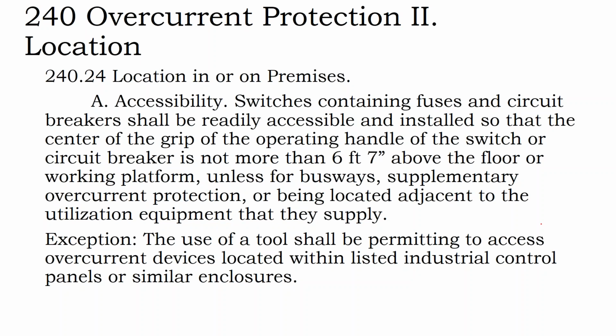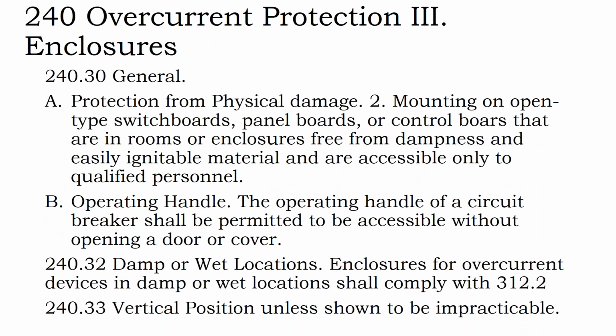Okay, so accessibility: your breakers and switches should not be more than 6 feet 7 inches above the floor or working platform. So when you're doing your electrical design layouts, the general philosophy is make sure that you have enough working space so that anyone can access the switches and handles, and also make sure that your non-electrical scope stays far away from your electrical scope. We see requirements like, on the outside of the building, a 3-foot distance. It's not so harsh in your control room. You need that 30-inch width working space in your electrical zone. But generally, you don't want to combine. You want to keep your plumbing away from your electrical. You want to make sure you have plenty of space to operate, and then you won't get any code violations in your array layouts. It gets harder when you don't have unlimited space to deal with.